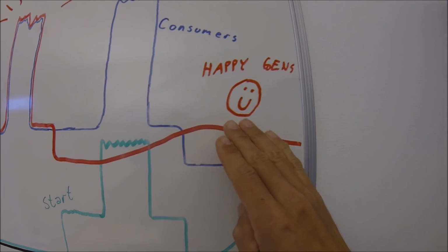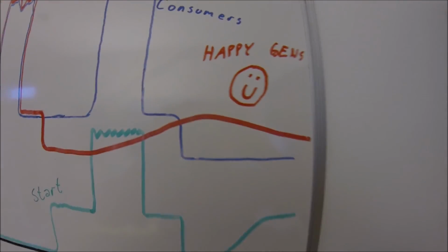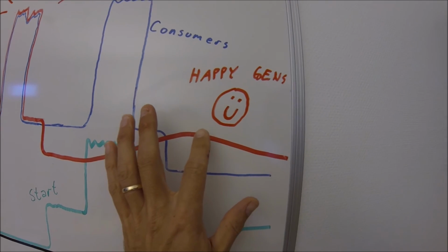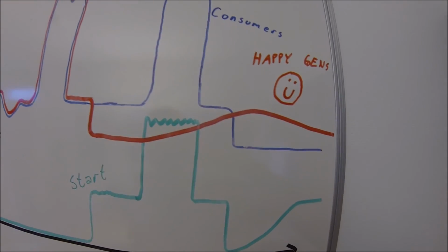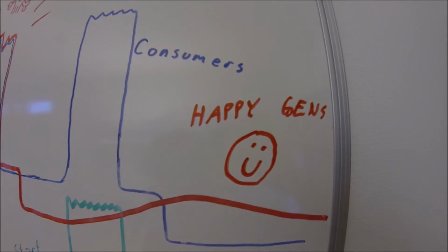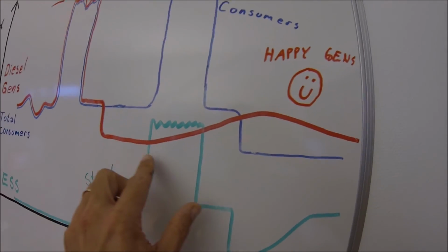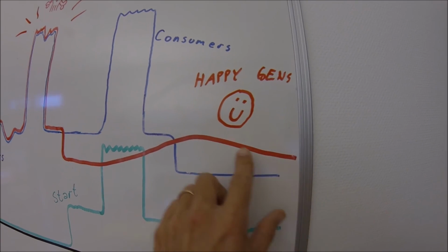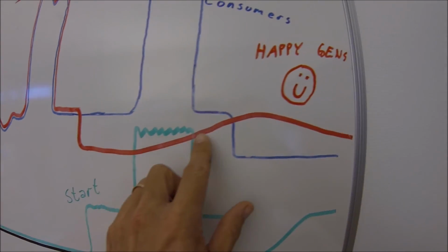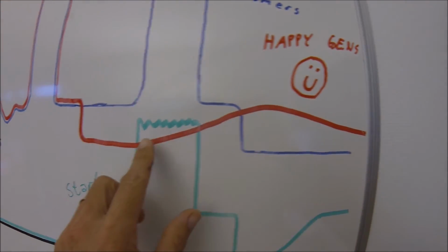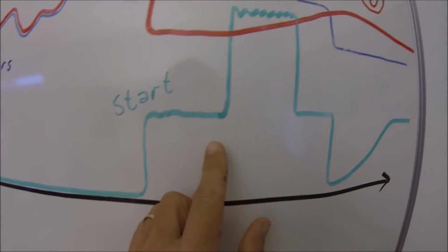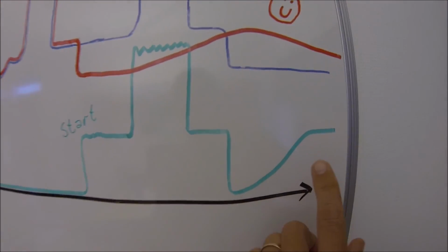You need to replace the battery state of charge, so it sits there with some load to replace that energy in the battery. But basically, the generator sets are happy with this. This is how a diesel generator or liquid natural gas generator wants to work, in a soft, nice way. And you have the battery and power electronics working fast and abrupt. The base current reference is almost immediate response in the active power.